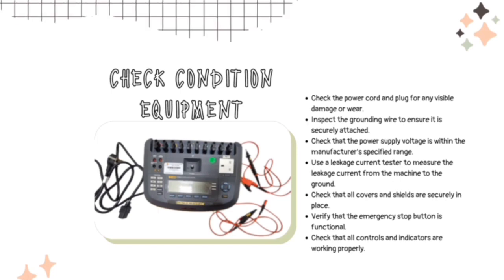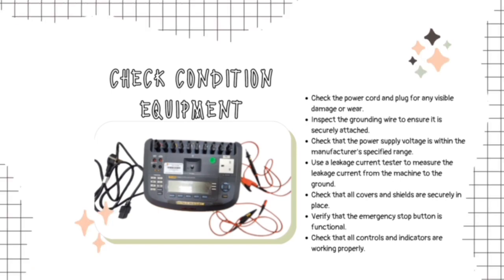First of all, we must check the condition of the equipment, which is ESA 632. Firstly, check the power cord and plug for any visible damage or wear. Then, inspect the grounding wire to ensure it is securely attached. Next, check that the power supply voltage is within the manufacturer's specified range. Next, use a leakage current tester to measure the leakage current from the machine to the ground.